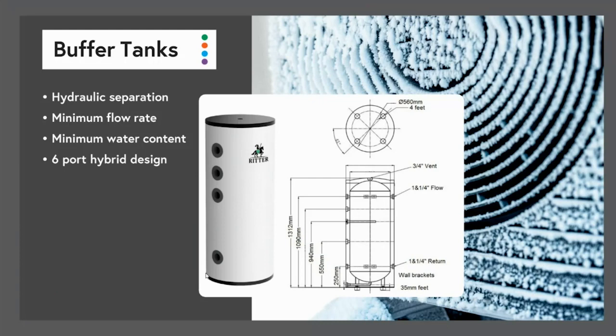What the buffer tank also does is maintain minimum flow rate. Heat pumps generate heat and they must dissipate it to the system. If there's not enough flow rate going through the exchanger, the heat pump will overheat the compressor and have to shut down, and that's called short cycling. Heat pumps that have compromised system designs suffer from this, and that will reduce their lifespan dramatically.